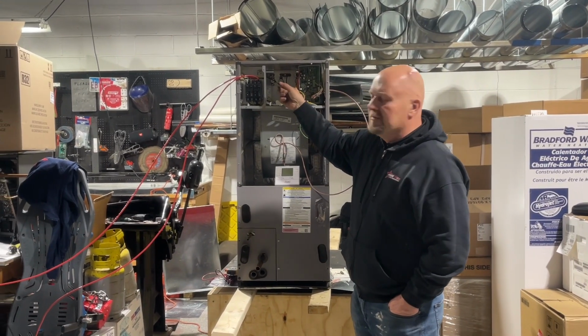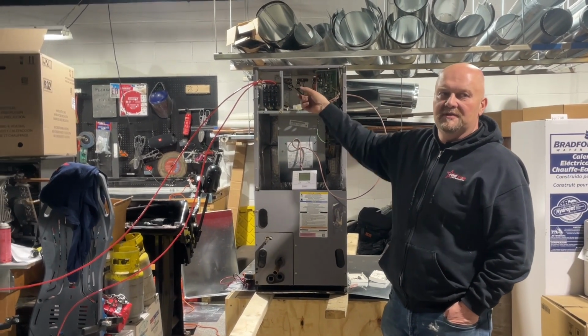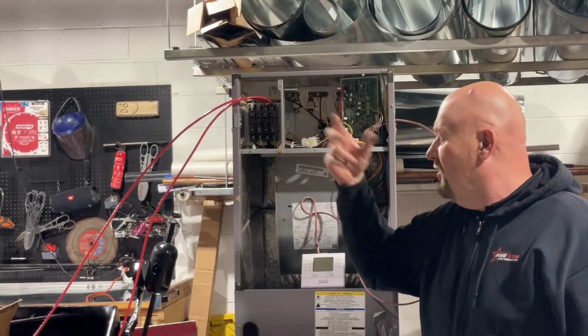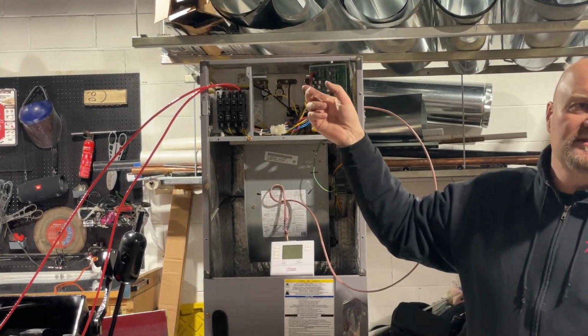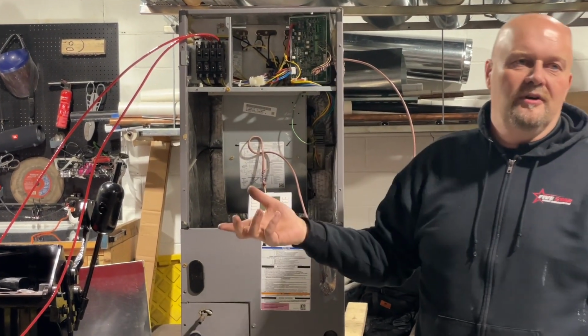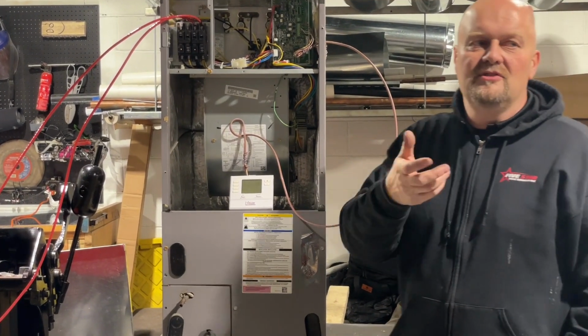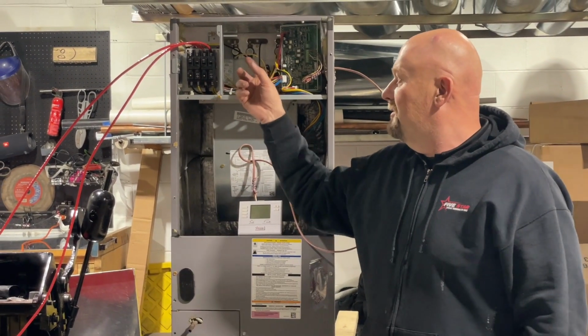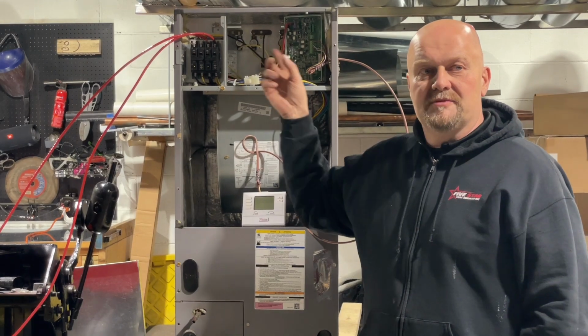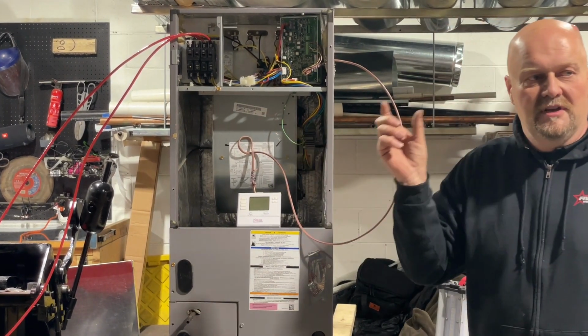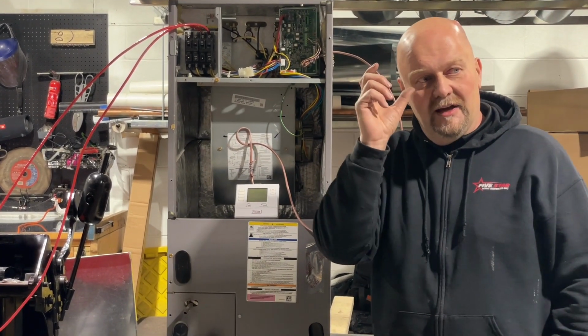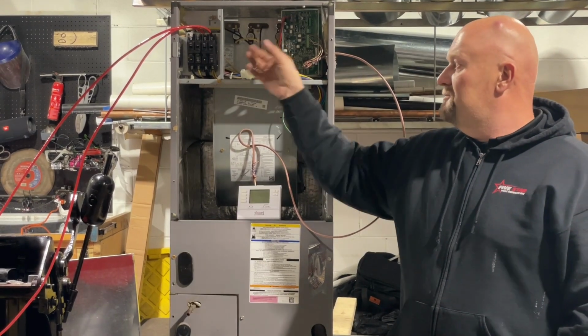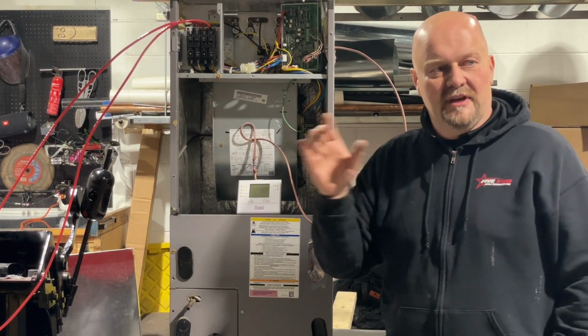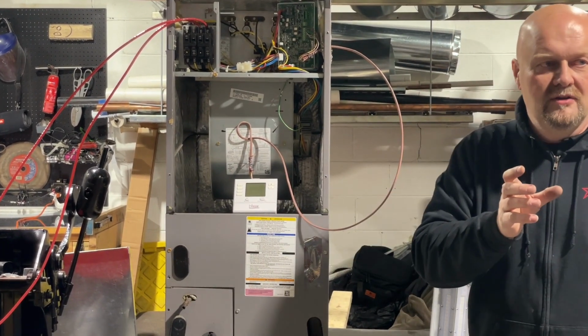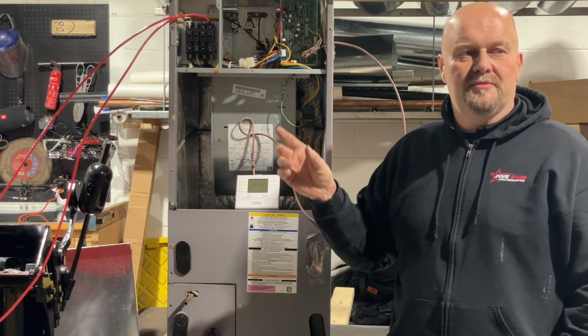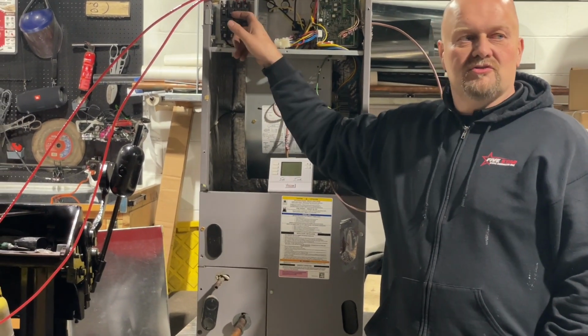Those are much softer, nicer relays. The one with a time delay inside, or old school traditional sequencers that work on temperature. They warm up to close, like we talked about before. And the reason you would have an old school heater with multiple electric strips together, you would have sequencers that don't get engaged at the same time. If you have 3 of these heaters and you want to bring them all on at the same time, you really don't want to do that.